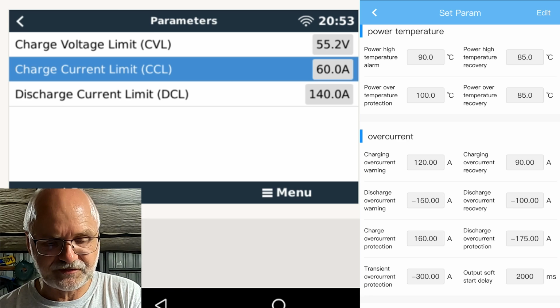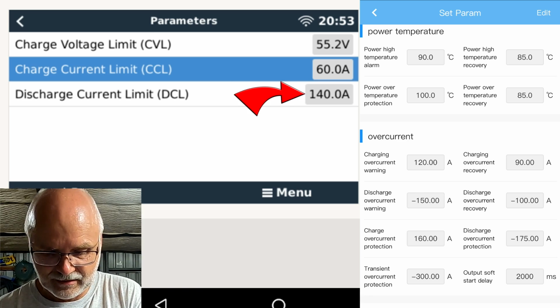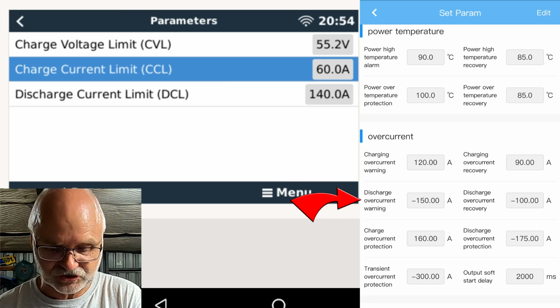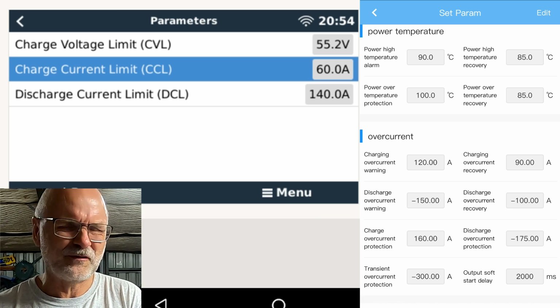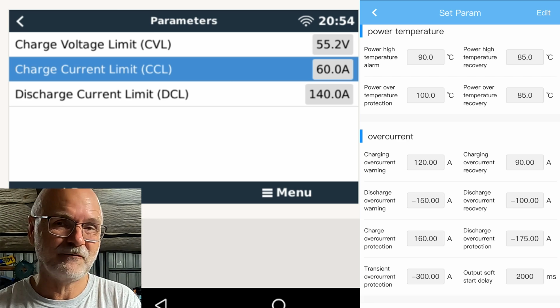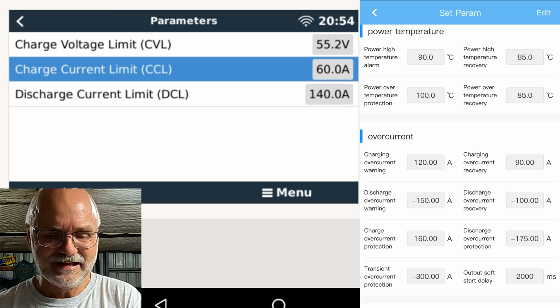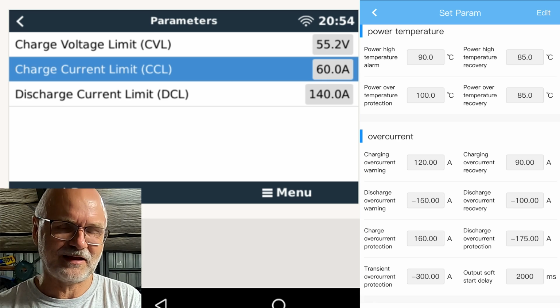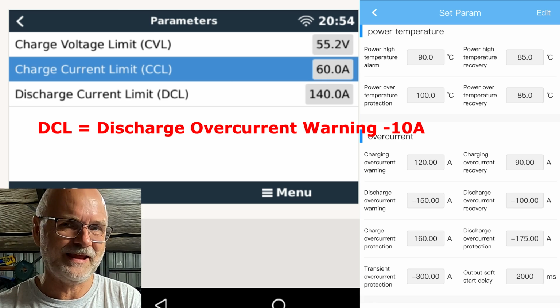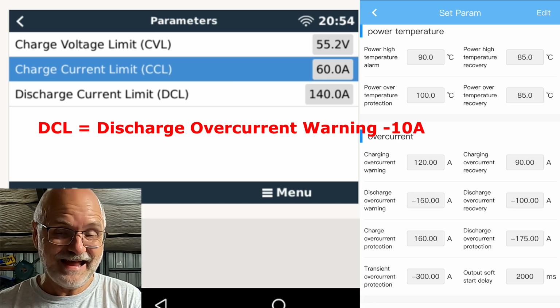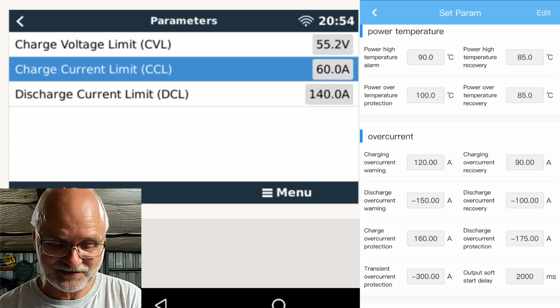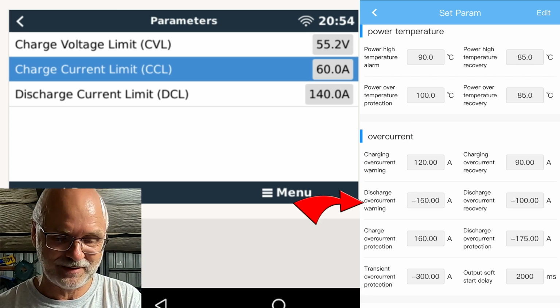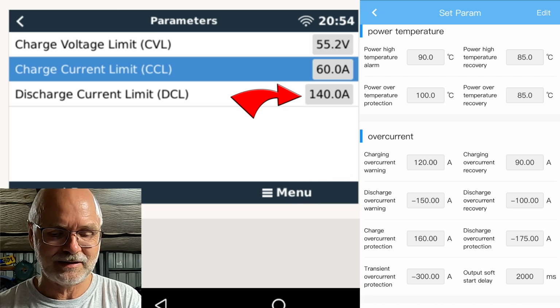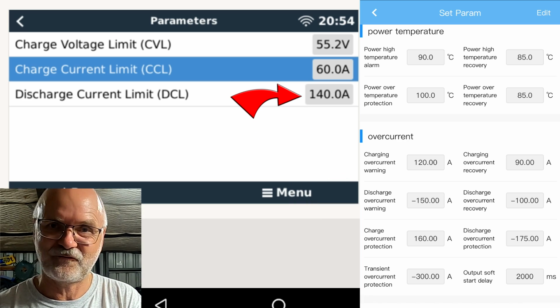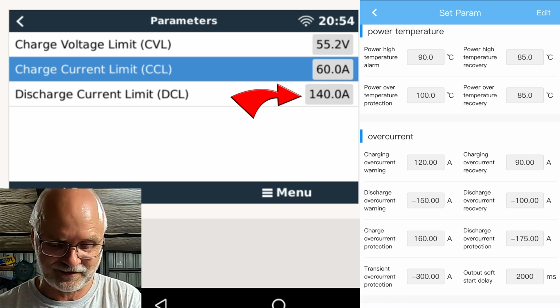Okay, next parameter is the discharge current limit. So obviously this is the discharge overcurrent warning then, right? And here it is a different formula. Well, for charging, it is half the current we are setting in the BMS. For discharging, it is the exact value minus 10 amps. Again, I don't know why that is, but you can see I have set 150 amps here in the BMS, and the discharge current limit, DCL, shows 140 amps only in the Victron system.